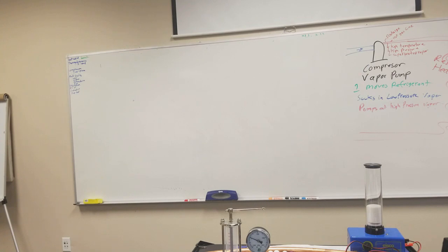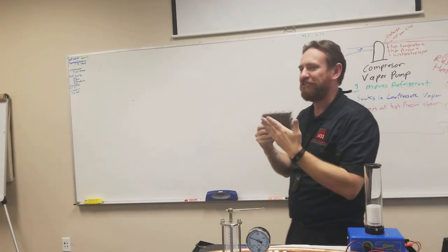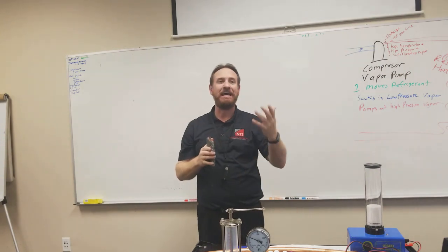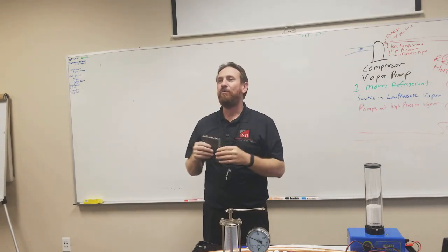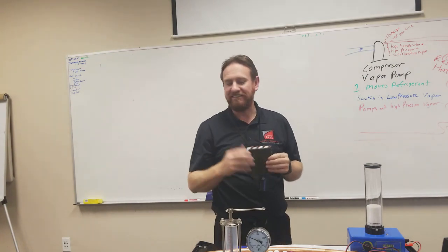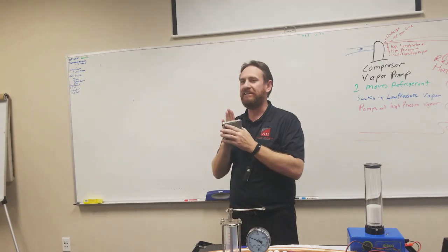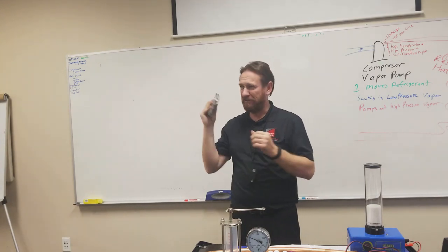And I don't want to add heat to it, I want to get the heat out of it that I already have. So I do that by increasing the pressure. By increasing the pressure, I increase the temperature. Now the heat wants to leave the refrigerant to get outside. And I'm moving air across this, so the heat's leaving the refrigerant through the coil into the air. So the air is coming out of the unit warmer, because the heat's leaving the refrigerant going to the air. The refrigerant coming out of this is cooler, less heated. Make a little bit of sense?